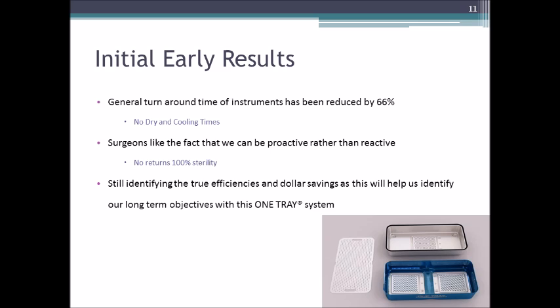On the next slide, the general turnaround time of instruments was reduced by about 66%. No dry and cooling times. So, like I mentioned, that whole 45-minute cycle is reduced out of the equation. The surgeons like the fact that we can be proactive rather than reactive, so that we're essentially providing them a 100% sterile device, whereas in the past that wasn't always a guarantee, if you will. We're still identifying those other efficiencies and dollar savings. Long term, we're trying to quantify all that, and we'll share those results as I get them online.